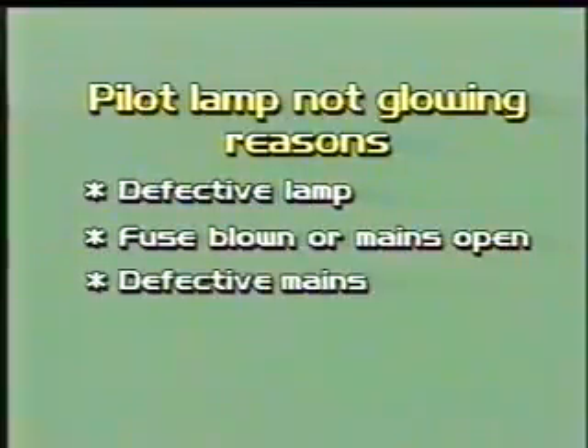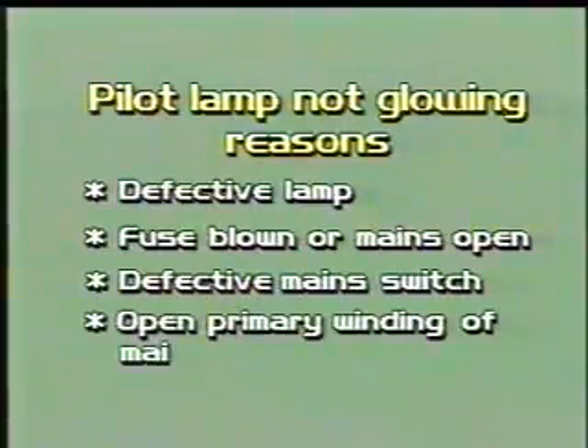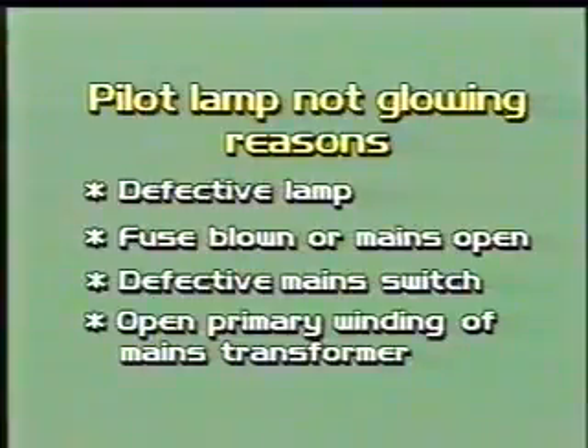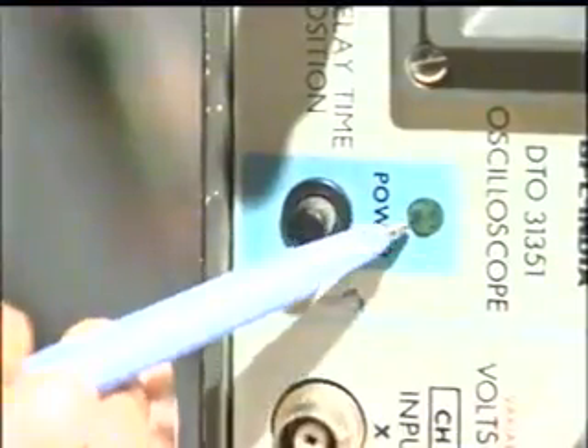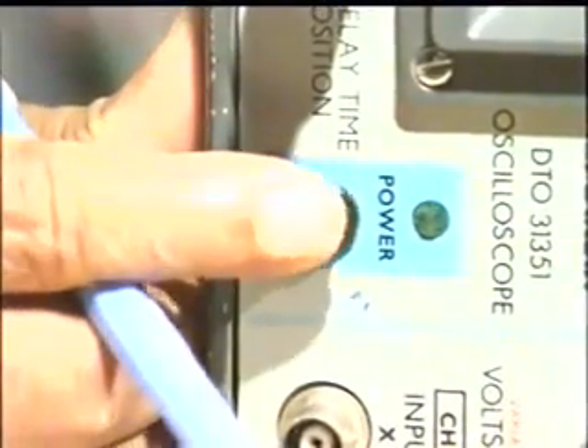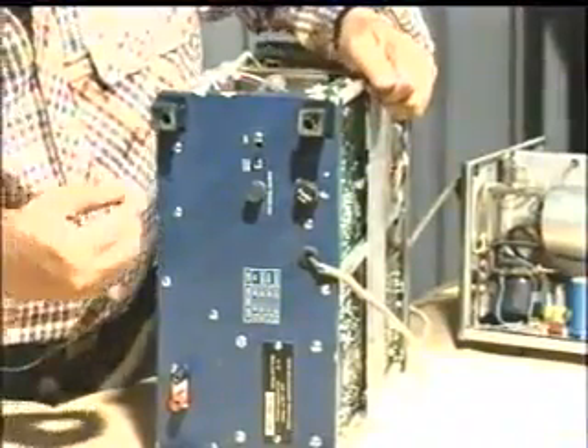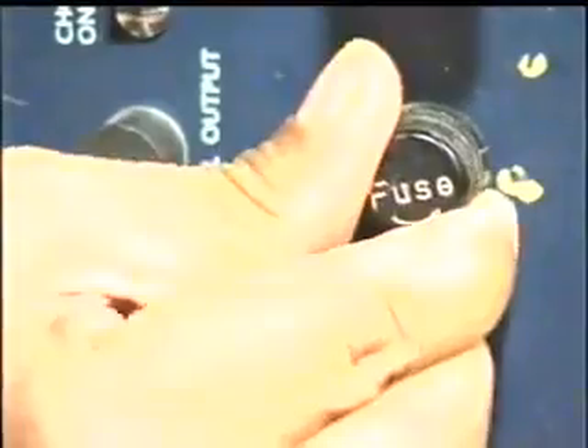If the pilot lamp of this defective oscilloscope is not glowing, check the following suspected components: defective lamp, fuse blown or mains lead open, defective main switch, open primary winding of the main transformer, and these components are here in this oscilloscope. Pilot lamp, fuse, defective main switch.